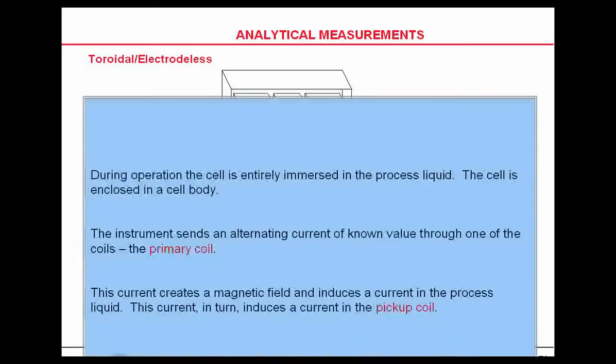This is what's called electrodeless conductivity. During operation, the cell is immersed entirely in the process liquid. The instrument sends an alternating current of known value through one of the coils — the primary toroid. This current creates a magnetic field and induces a current in the process liquid, which in turn induces the current in the pickup coil.